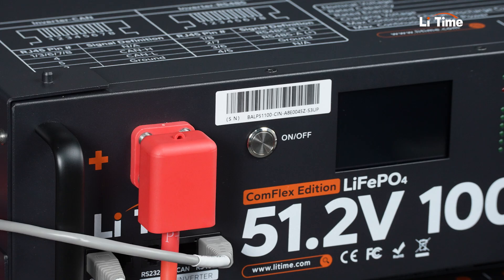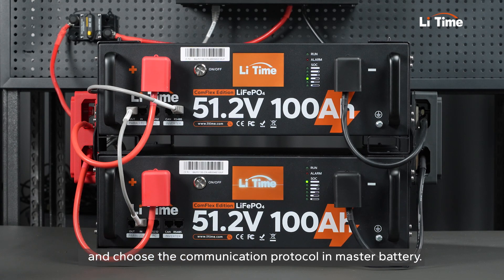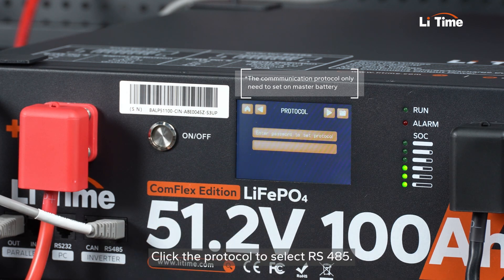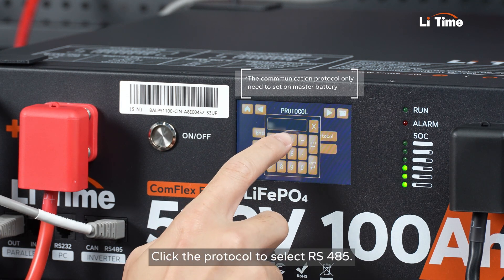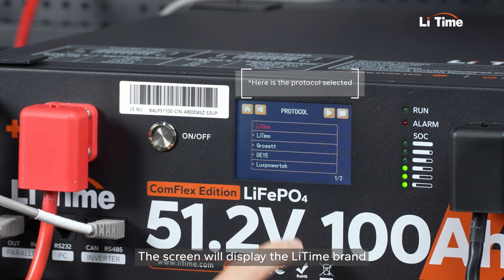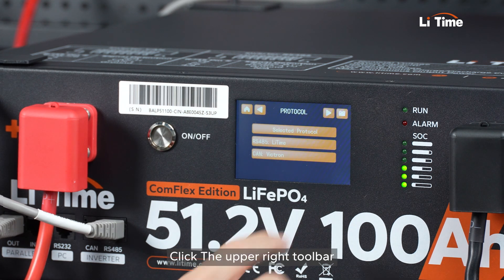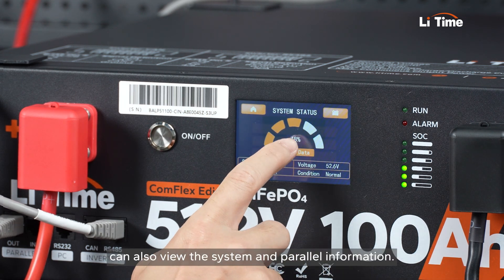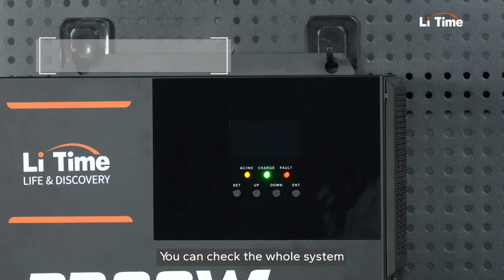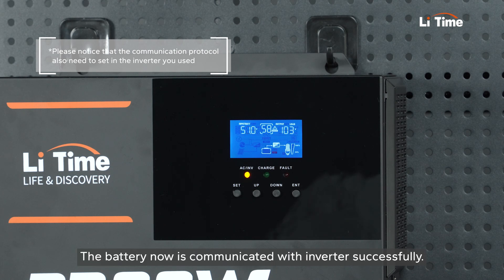Here we come to the last step: set the communication protocol. Turn on the batteries and choose the communication protocol in the Master Battery. Touch the display screen to enter the home page. Click the protocol to select RS-485. Enter the factory password to successfully connect the inverter — the screen will display the Li Time brand. Click the upper right toolbar; you can also view the system and parallel information. Now open the breaker. You can check the whole system information in Master Battery. The battery is now communicating with the inverter successfully.